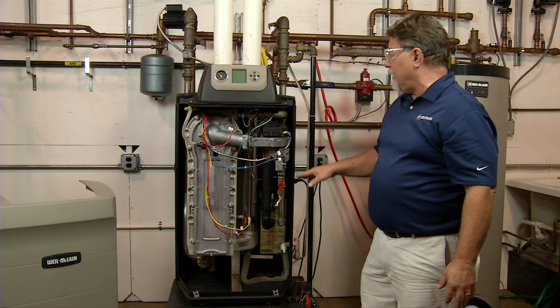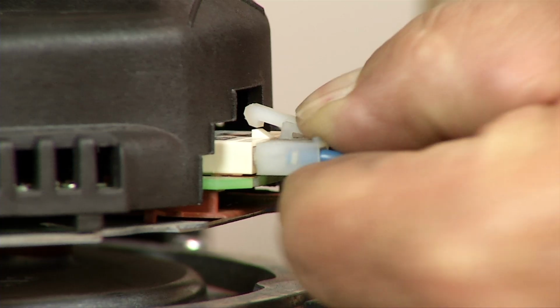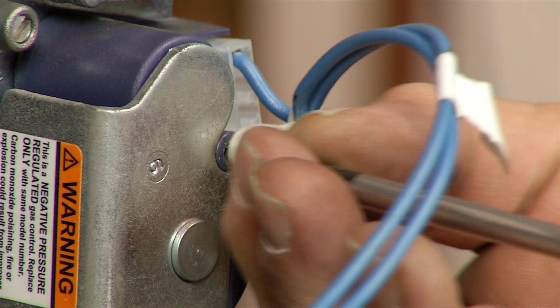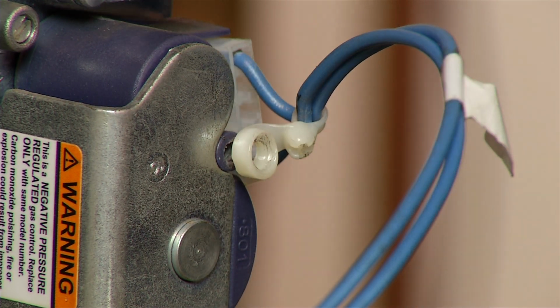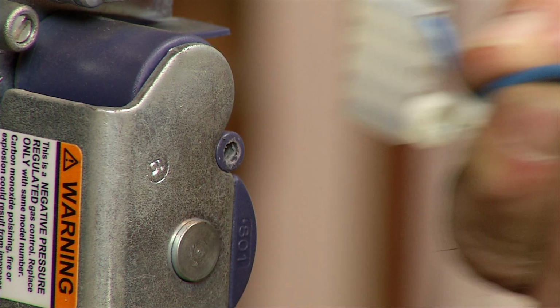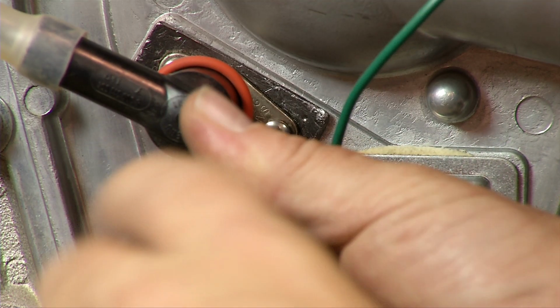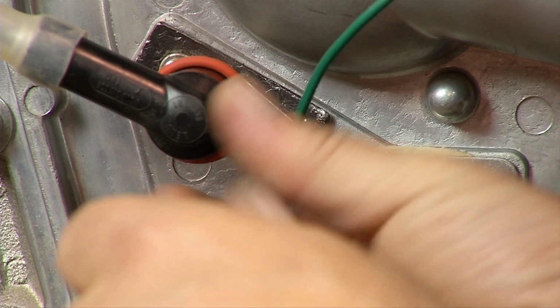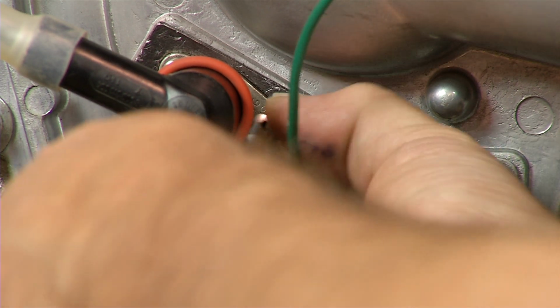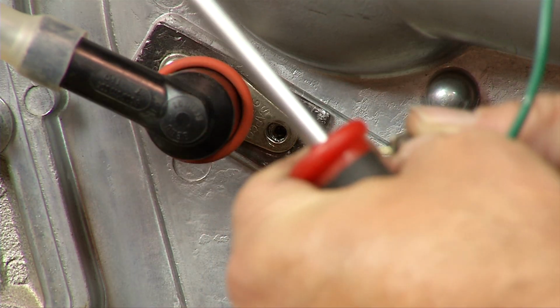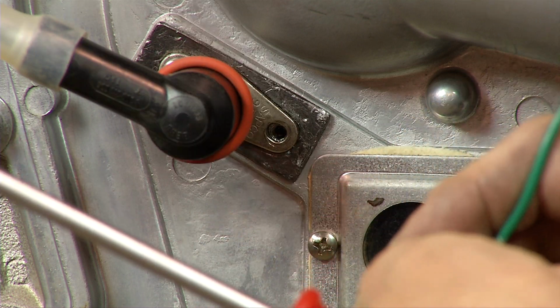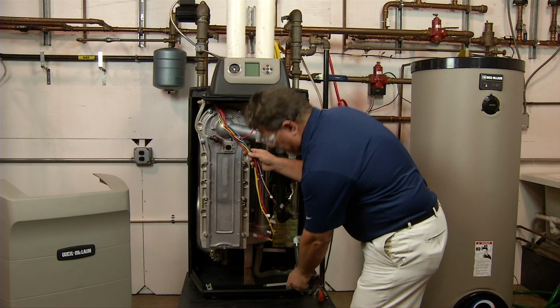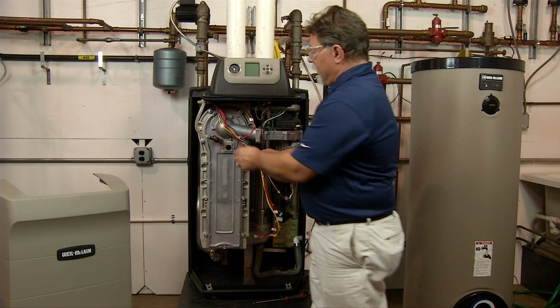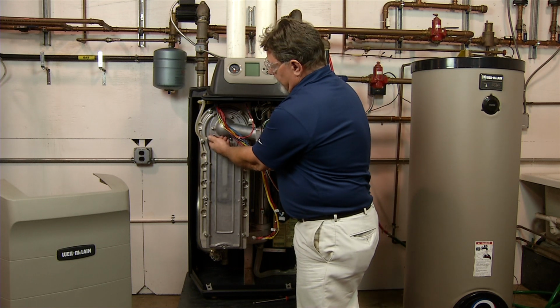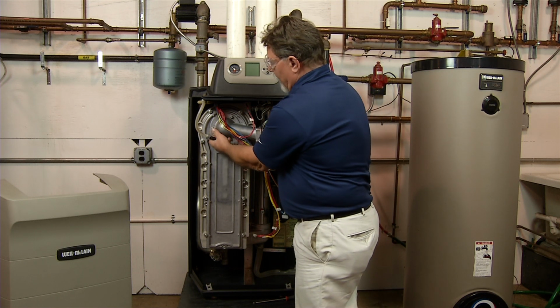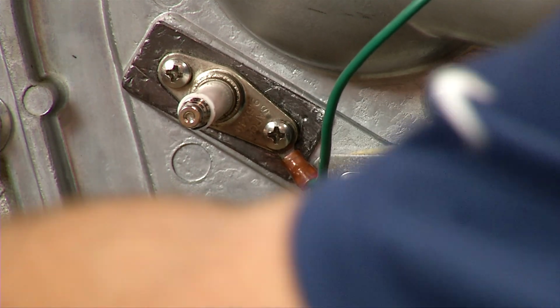The first thing that we want to do is actually remove the wiring harnesses connected to the components on the boiler. There's one other wire that we do want to remove at this point, and there is a ground wire that is connected from the chassis of the boiler to the igniter. The other wire that we want to remove is the ignition cable, and that simply pulls off the igniter, and we'll just set that aside.